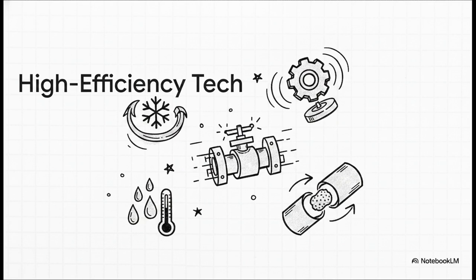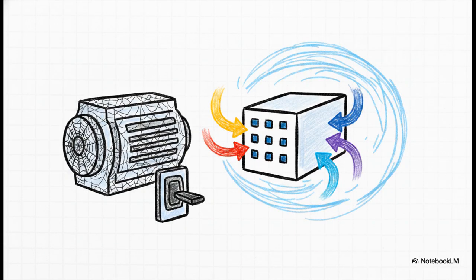Don't worry about the heavy jargon, let's just quickly break down why these are so brilliant. First up, high-chilled water and free cooling. Back in the day, data centers needed icy 7 degrees Celsius water to cool servers, but modern AI servers can handle much warmer water, sometimes 15 to 22 degrees or even hotter, and that is a total game changer. Why? Because it means they can just use cold outside air to cool the water for most of the year.